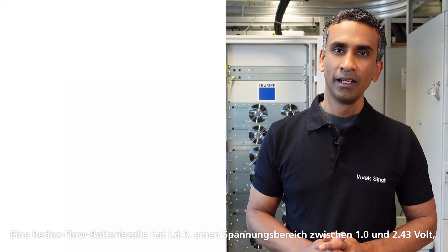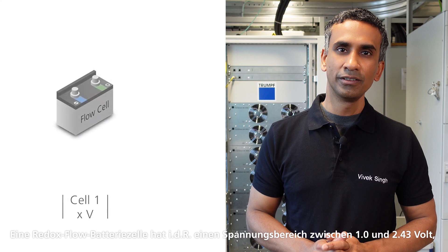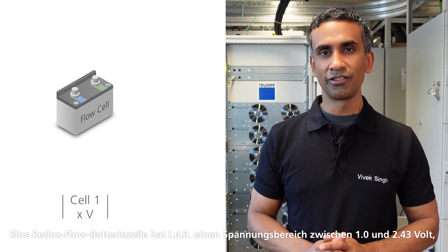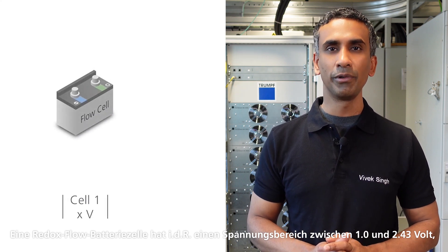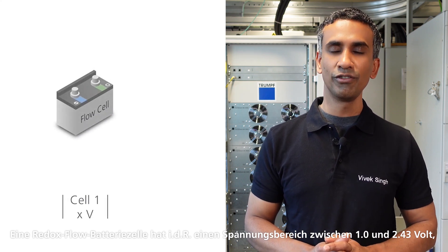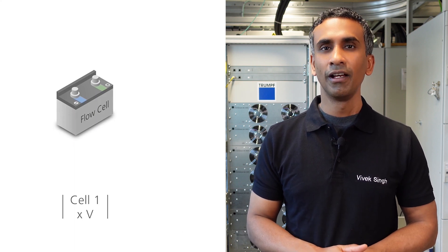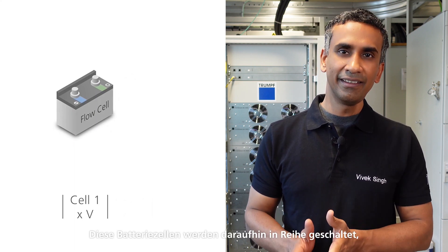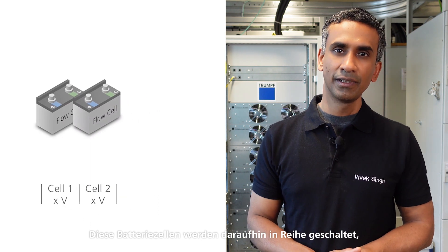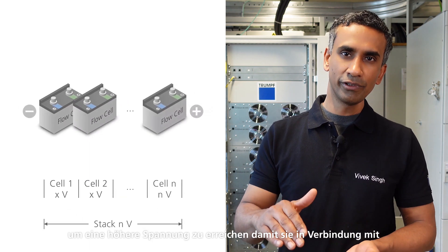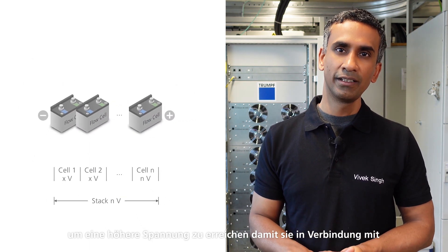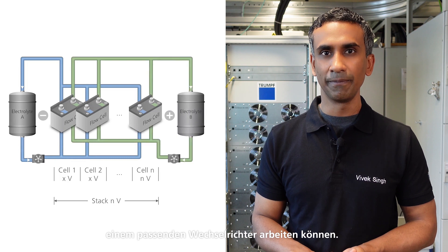The first concern that flow battery manufacturers have is what is the right optimum stack. A typical nominal cell voltage range of a flow battery can be anywhere between 1 to 2.43 volts, depending on the kind of flow battery used, and then these cells are stacked together to reach higher voltages so that they can operate in conjunction with a suitable inverter.